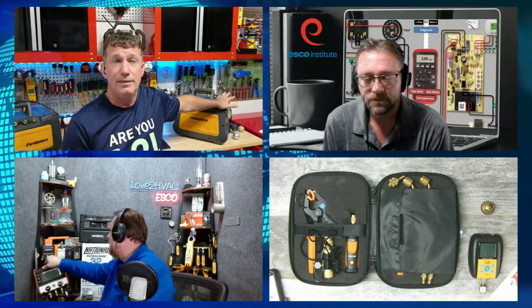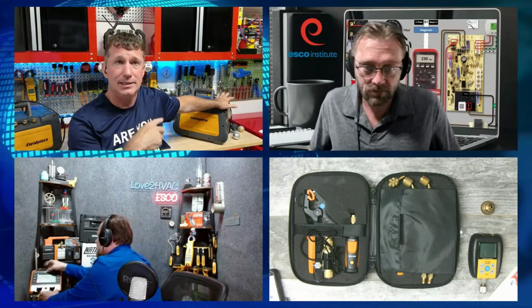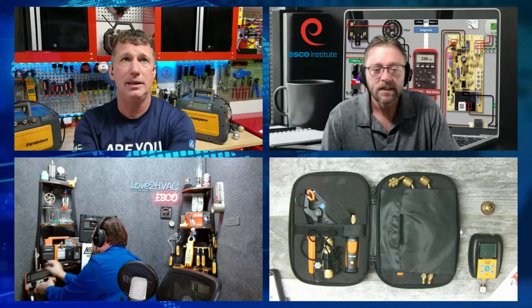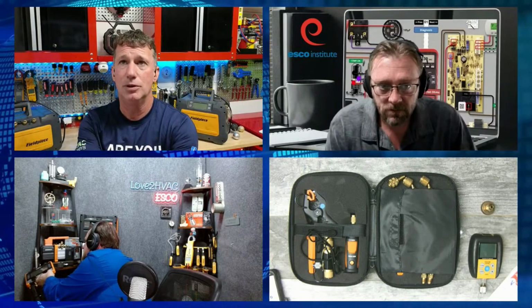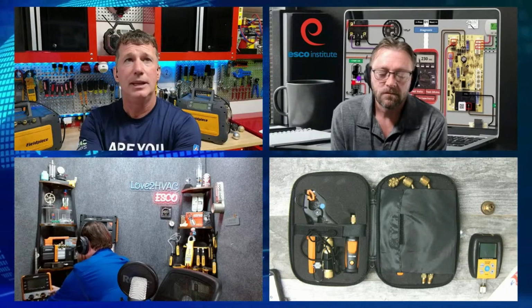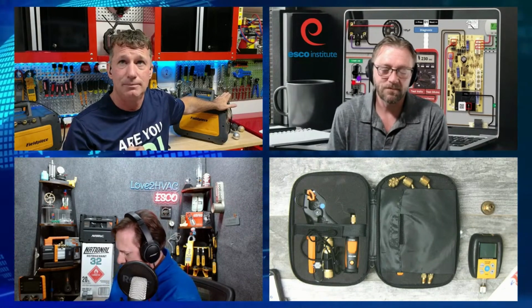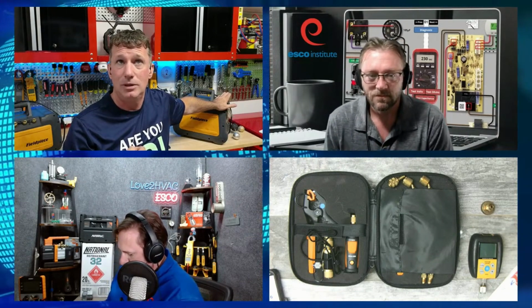My MR45 has had one update since this was manufactured. One of the requirements that we get out of 740 is that the A2Ls are not drawn into a vacuum during refrigerant recovery. So the updated MR45 actually has a shutoff at 0. At 0, it will shut down the process. If I use my existing MR45 that does not have that function, but I personally manually shut the unit off at 0 and follow best practices, am I A2L compatible?